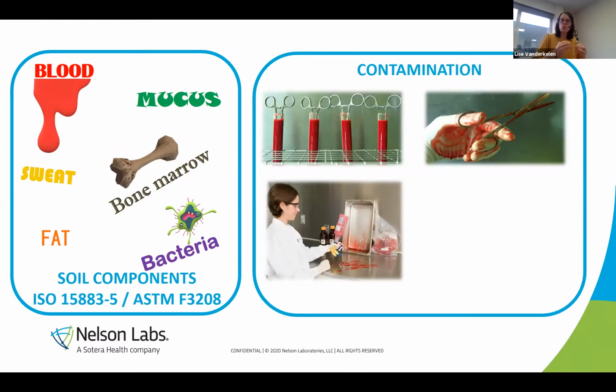You have to select a worst case contamination. You have to challenge your device in the soiling, but not too worst case. For instance, in these pictures, you see the scissors. Only a part of the scissors is submerged in the soil, not the complete device, because that's too much. That's not clinically relevant anymore. And you're going to use the handles with soiled gloves, or you can spray the device.